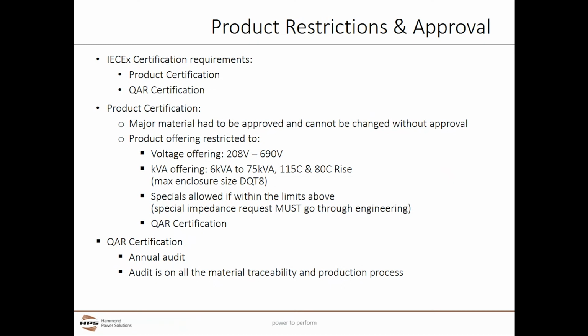Specials, we do have specials, and they are allowed as long as they are within the limits below, within the actual voltage and kVAs and the maximum enclosure size. All of our specials will have to go through our engineering to make sure that they are actually within the limits of the certification. The additional part of this certificate is also QAR certification, which assures the customers that the product that we build is built according to this certificate. There are annual audits that they will do, as well as an audit on all of the material and production processes. All of the material that we purchase for this product also has to have traceability, and they check for that.